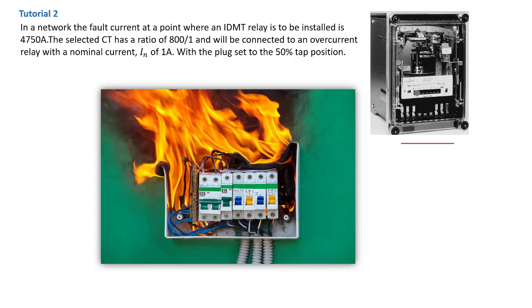This is a distribution box, but this could be bigger if it happened in a transmission or distribution substation. This tutorial is very similar to the previous one, tutorial 1, where we were also asked to calculate the multiple of setting current with the stated fault current flowing. Here, the stated fault current has changed, and also the current transformer ratio has changed.